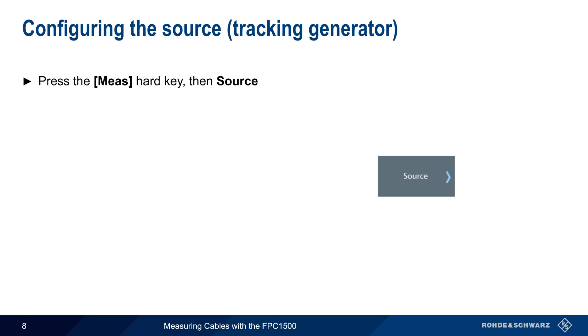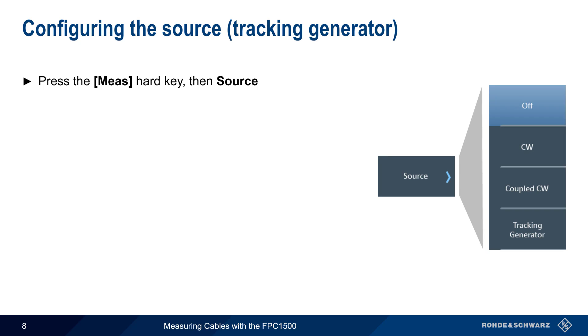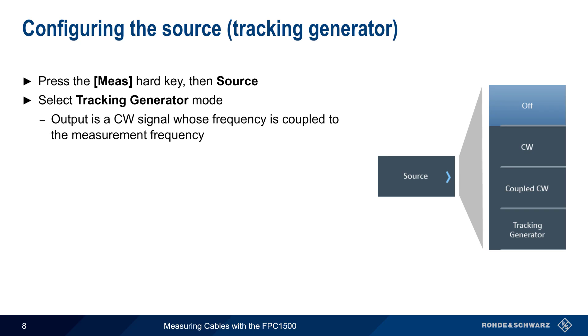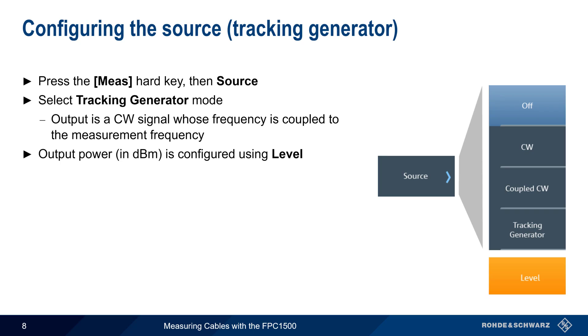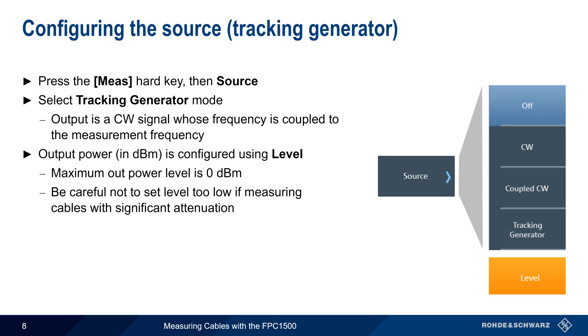To configure the FPC's tracking generator, press the Measure hard key and then Source. For cable measurements, we want Tracking Generator mode, in which the output of the generator is a CW signal whose frequency is coupled to the measurement frequency. That is, the source output frequency sweeps at the same rate as the measurement. The output power of the generator is also configurable in units of dBm using the Level key, with the maximum output power level being 0 dBm. Care should be taken not to set the tracking generator level too low when measuring cables with significant attenuation, as this can lead to inaccurate results.